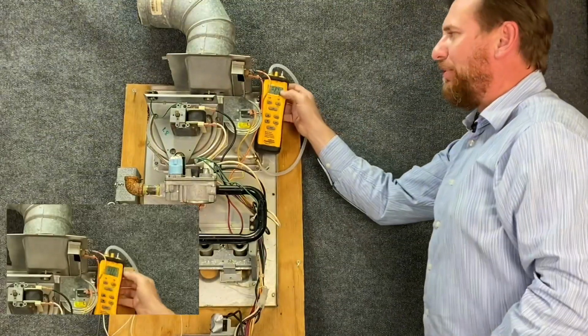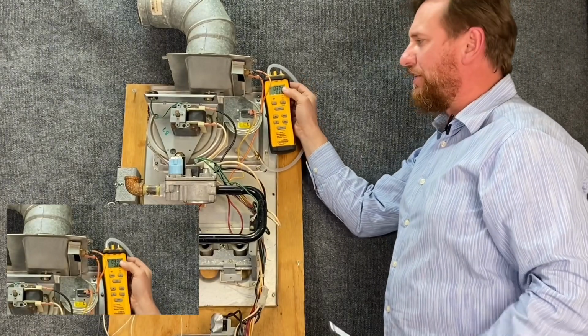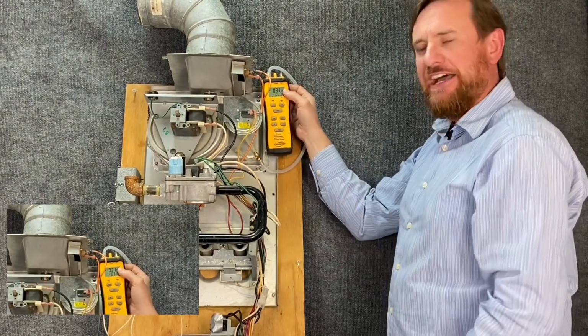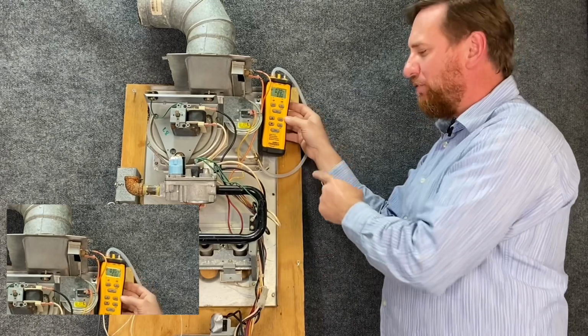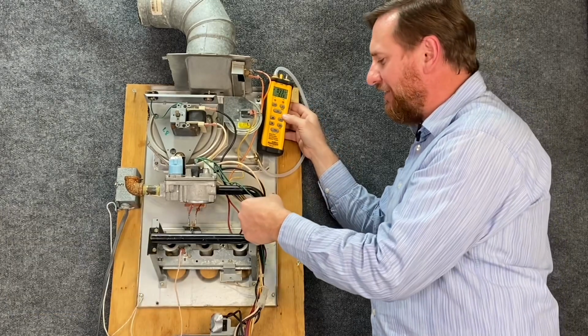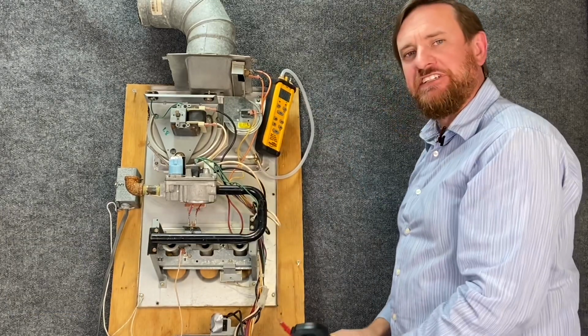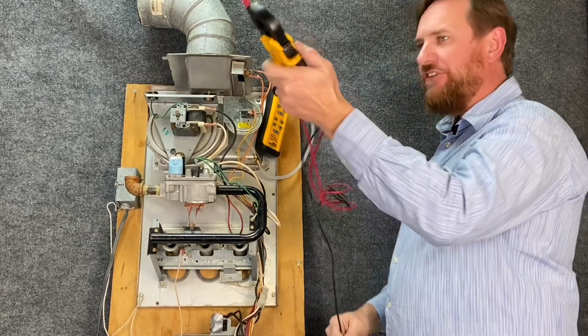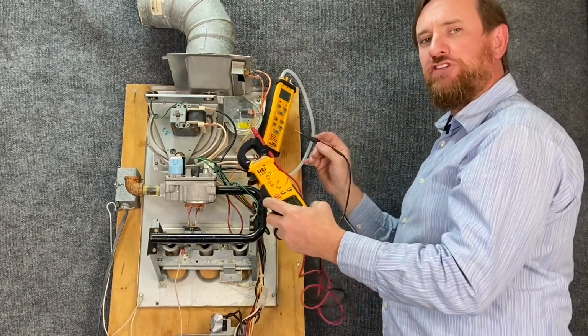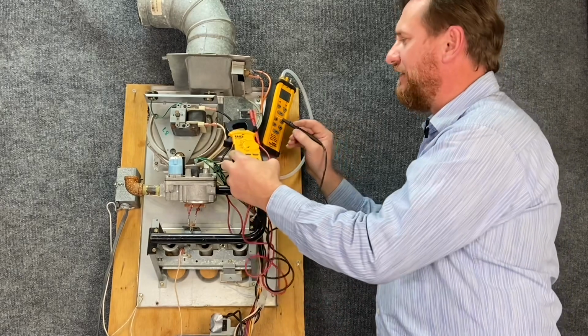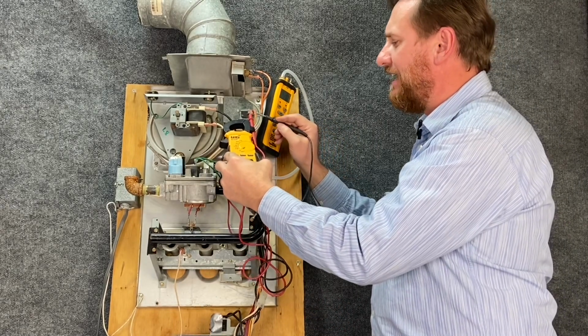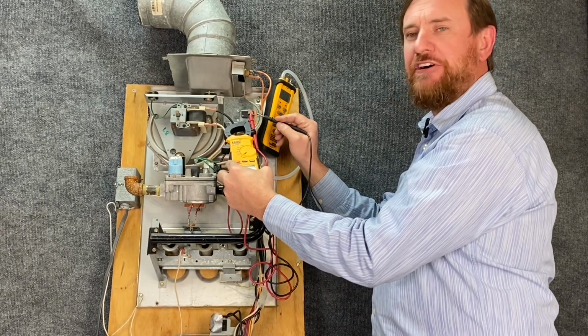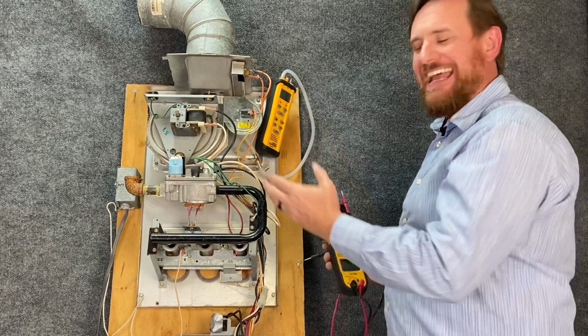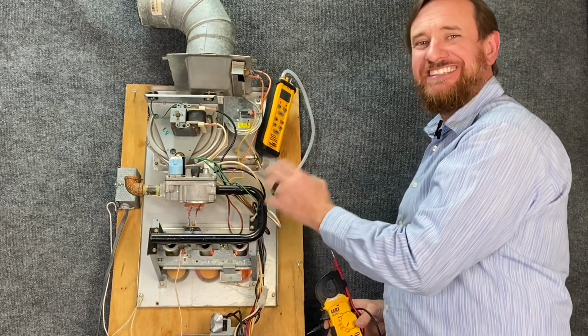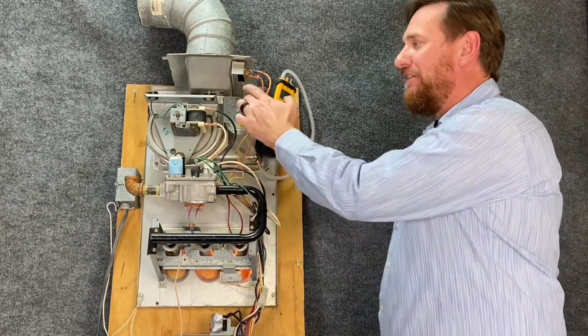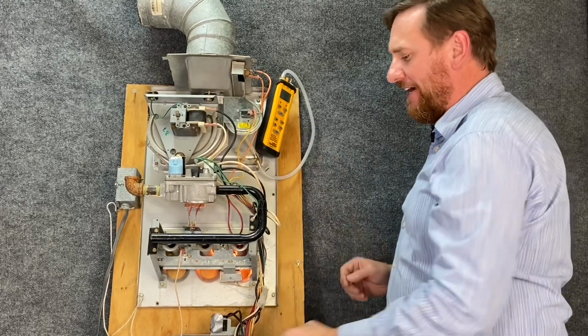Now we can see I'm pulling 0.34 inches of water column. It closes at 0.25. There's two ways I can now see if that's working. One way is I can look down and see if my hot surface igniter starts getting hot. The other thing I can do is check voltage. With the switch closed, I should have 0 volts. Put the meter on one side and then the other, I'm showing 0 volts. So the switch is now closed, and down below our hot surface igniter is getting hot. So we know that that can't happen until the switch closes. So that's a good sign.